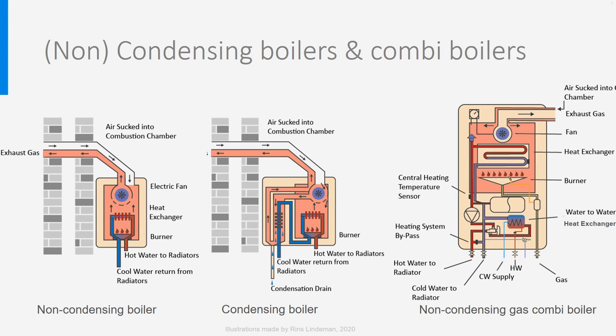A combi boiler may be found in condensing and non-condensing designs. An additional heat exchanger is placed for hot tap water heating. When there is a demand for hot tap water, the hot water flow to the radiator is diverted to a water-to-water heat exchanger, where it gives its heat to the cold tap water (CW), which is heated to produce hot water (CHW). Because the demand for hot tap water is generally for a short time — a few seconds at a kitchen tap to 15 minutes in a shower — people won't notice that the space heating has stopped.